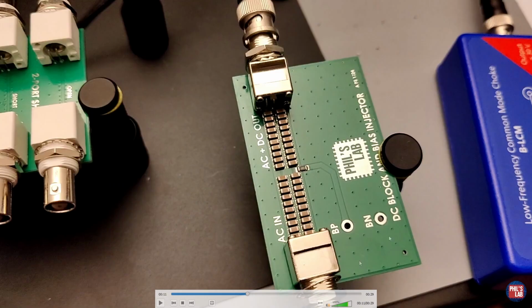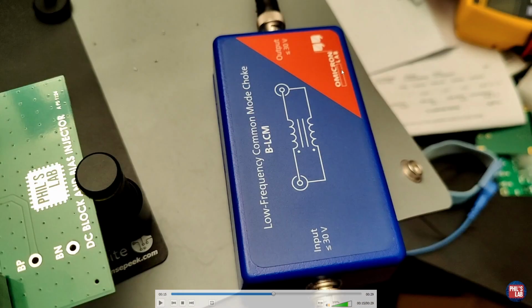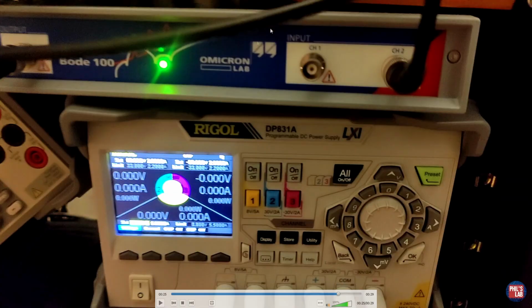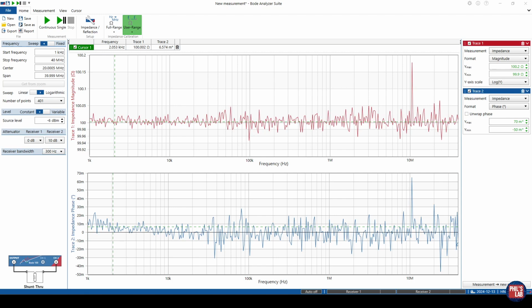From the output, we then feed into another DC block and bias injector, except now I'm not applying any DC bias to this 10K resistor, so it's floating. I could of course desolder it to make it a bit neater, but this is now just acting as a DC block, not a bias injector, to remove that DC offset before we feed it into the low frequency common mode choke, again to suppress ground loop errors, before we go back to the Bode 100 into the channel 2 input port. I'm now in the Bode Analyzer suite.